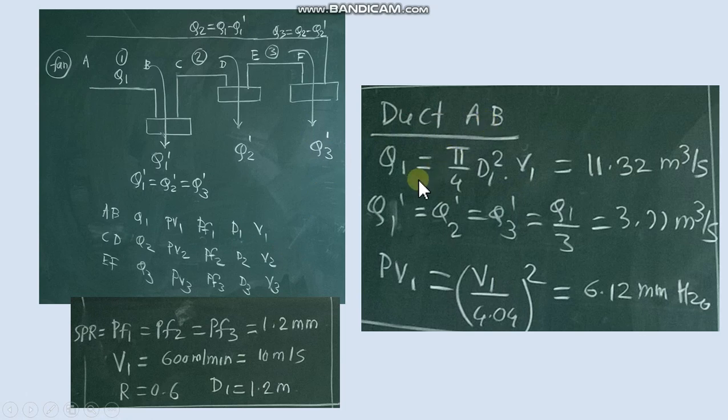In duct AB, Q1 = π/4 D1² × V1. So diameter and velocity for main duct is given so we can calculate Q1. Now this Q1 discharge is divided into 3 parts equally. So we get at each end discharge as main discharge divided by 3 that is 3.77 m³ per second.